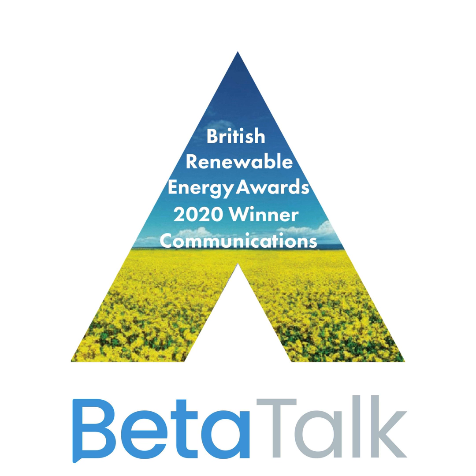Is this going to be something that's in a central plant station, or is this for people's individual spaces? That is one reason why we use PCMs, because it can be achieved, not as efficiently, with water storage as well, what we're doing. One reason we chose PCMs is because they take about half the space to store the same energy as a water cylinder, roundabout. And of course, still, the unit turns out to be big.